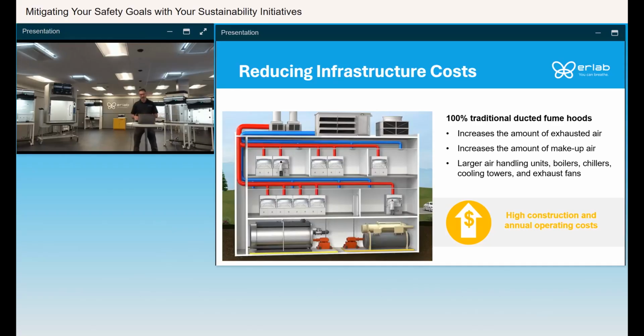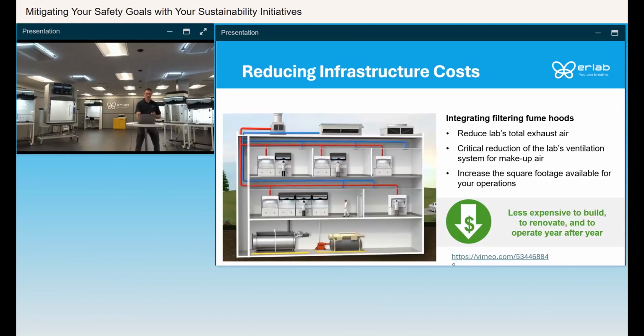Now take a look at the size of the chiller and the boiler in the basement, the air handling unit on top of the building, along with the exhaust fans and the cooling tower. And even look at the size of the ductwork. So these are 100% traditional ducted design. Now let's say you're looking to reduce your upfront costs and your operating expense. Well, maybe you can replace half of the ducted hoods with ductless hoods.